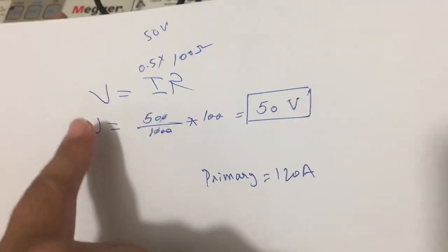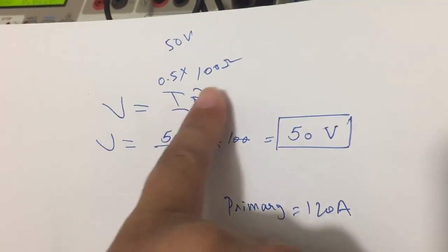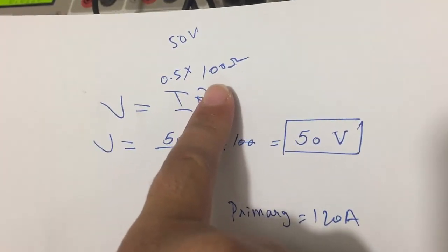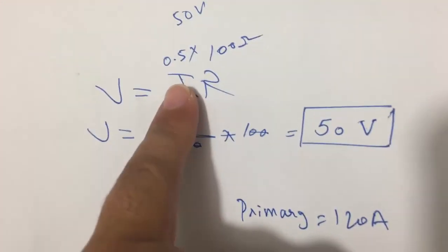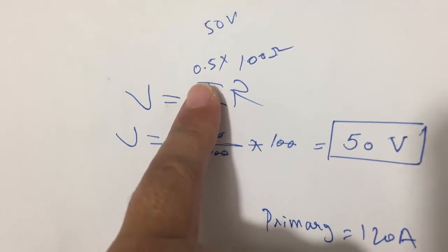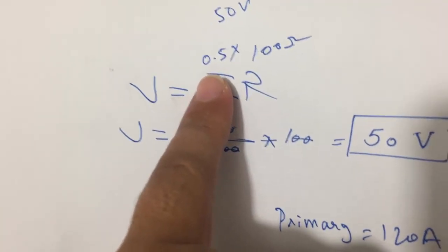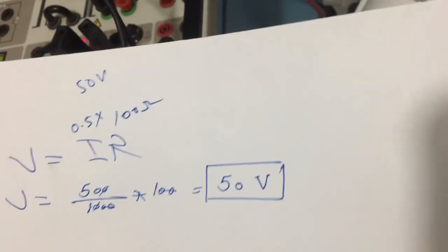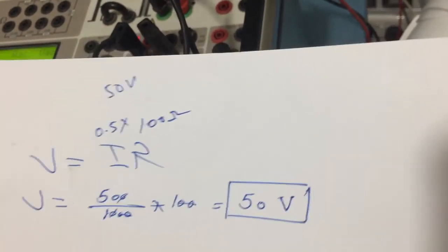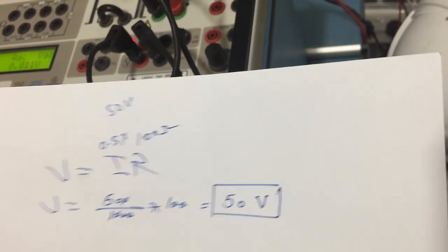Here is the formula: V equals IR. Our resistor in this circuit is 100 ohm, and the set current is 0.5 ampere, which is 500 milliampere. So V equals 0.5 times 100 equals 50 volts. By injecting 50 volts we get the set value for the REF trip. Now we will start injection by means of current.